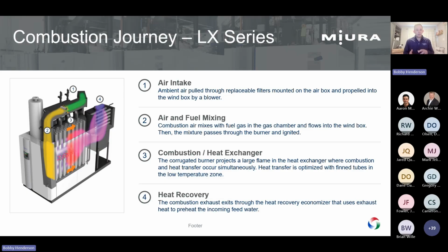It gives us a really nice design versus your traditional fire tube, where you've got your big tube sheets that see all sorts of different temperatures, and that expansion and contraction over time can create a lot of issues, especially if we're not treating our water well, and wear down over time and cause us to have to retube our boilers. And then, as you can see there, a built-in economizer on the backside.